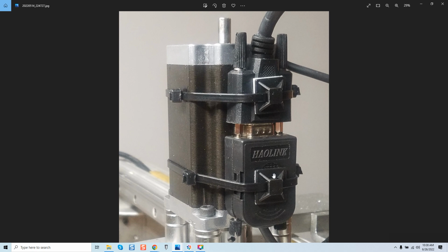So over time, again, it's not right away that it happens, and that's the big thing. Guys will connect their systems similar to this and think, oh, everything's great. And that's just for the first 1 or 2 hours. As soon as they get serious about their machine, start doing runoff production, they start finding out that as time goes by, intermittent connections start happening, weird things happen, they may go away, then they may come back, and I get a message, hey Vin, I don't know what's going on, I'm getting intermittent failure on such and such axis or multiple axis, and then I get a picture like this and we start covering details.